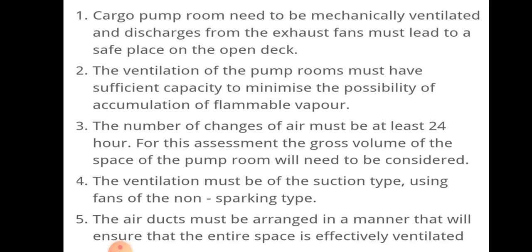The number of changes of air must be at least 24 per hour. For this assessment, the gross volume of the space of the pump room will need to be considered.